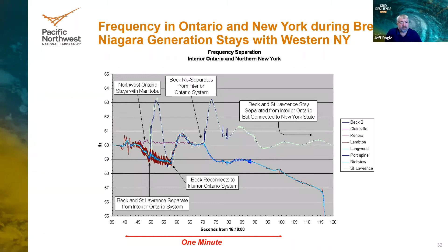This part of the system survived, and this diagram shows a really great illustration of how it broke up into multiple islands during that process. Many generators were tripped during that day. The good news is that none of these generators sustained any damage, so as soon as you got the grid back on, you could bring these generators back online and start serving load again.